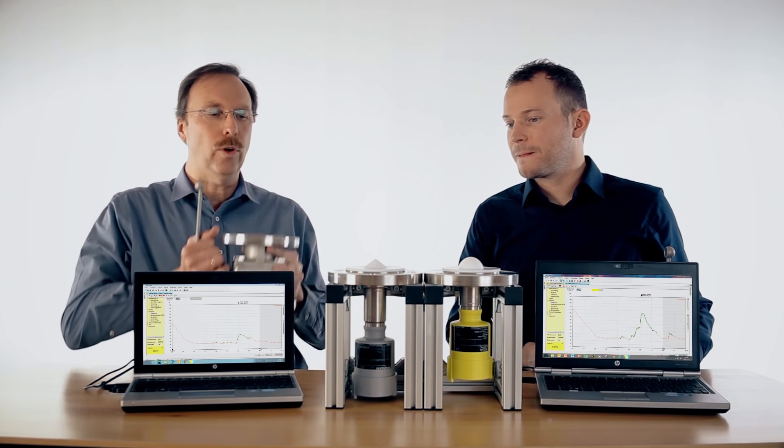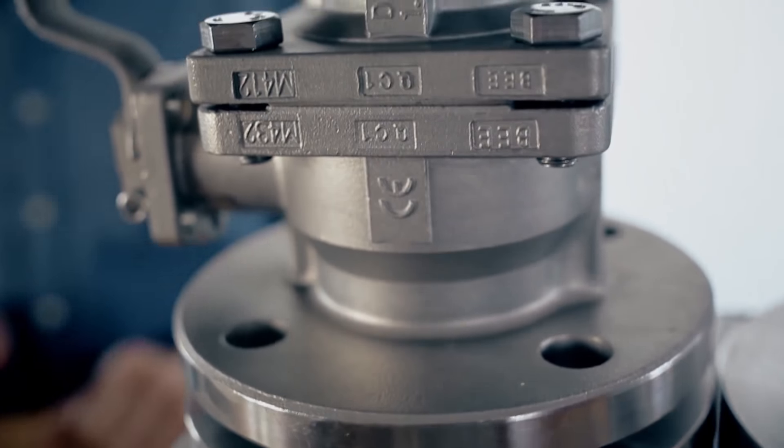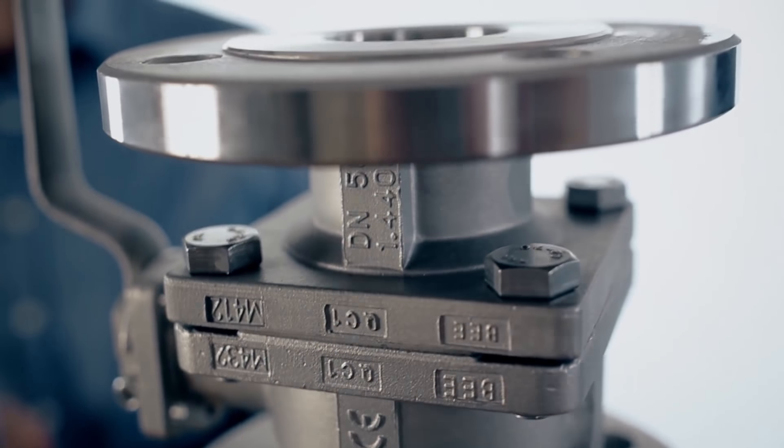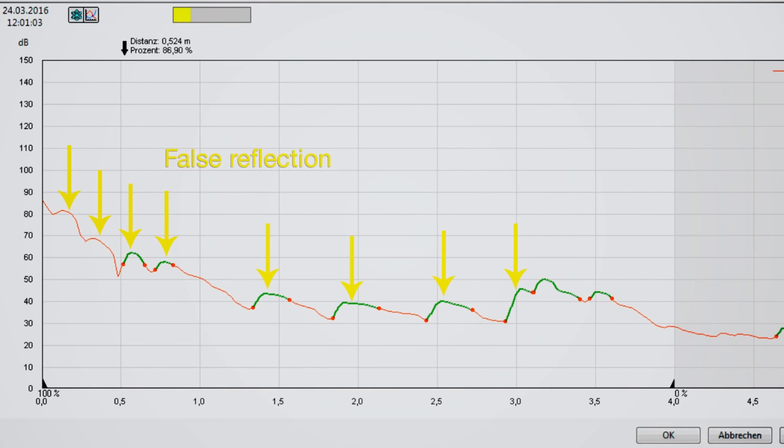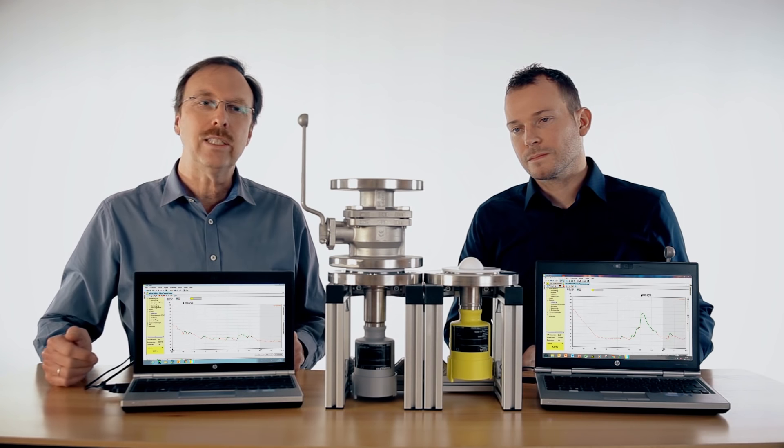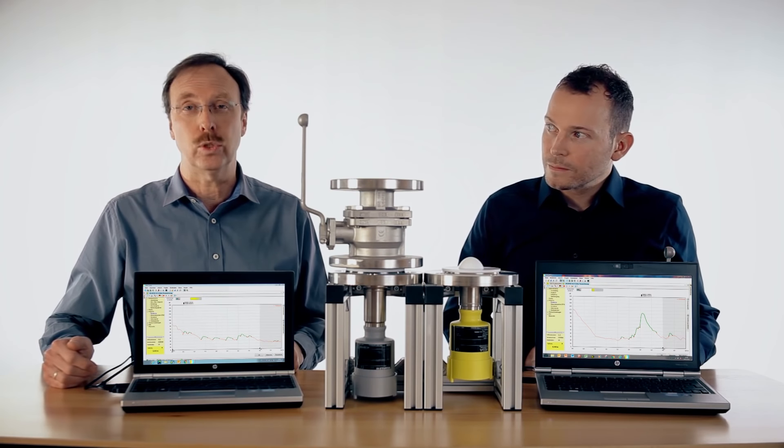Now let's put a ball valve on the sensor and have a look what is the influence. You can see a lot of noise, a lot of disturbances in the near range and the echo is also getting smaller. So in this application it is nearly not possible to measure over the whole range because we get so much disturbance.